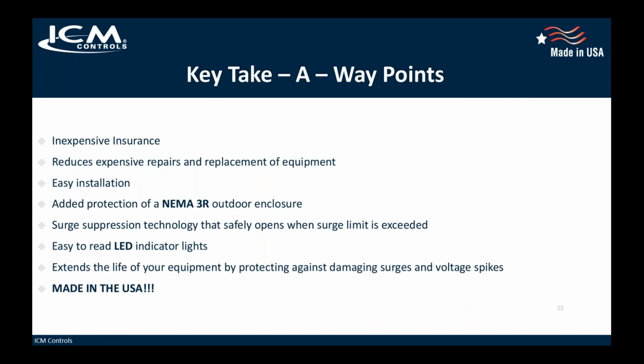Okay, so again, key takeaway points with our single phase surge suppression. It's a low cost insurance plan for your products. It reduces expensive repairs and replacement of equipment. It's very easy to install. It comes with its own installation guide, and it's just a few wires you tie in parallel with the line. You have a NEMA 3R rated outdoor enclosure. It's got TMOV surge suppression technology, meaning thermally protected metal oxide varistors, and easy to read LEDs. Not only does it extend the life of your equipment, but it protects you from those surges, which are taking out circuit boards in many cases. And of course, it's made right here in the USA, which is always a good thing, supporting our local economy.